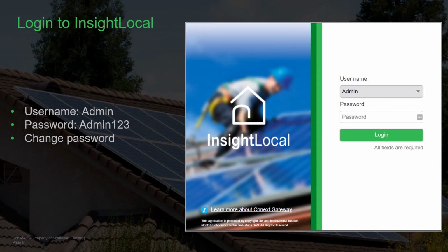Wi-Fi access point or Wi-Fi hotspot means InsightLocal is communicating directly with a computer. There are 3 different ways to get InsightLocal connected: hardwired, Wi-Fi station mode, or Wi-Fi access point. You will not have an internet connection in Wi-Fi access point mode, but it's probably the easiest means of connection to commission the system. Simply look for the broadcast Wi-Fi system in your list of available Wi-Fi networks, and then click connect, and you will be required to enter a password. This is located on a sticker on the back of InsightHome or InsightFacility.